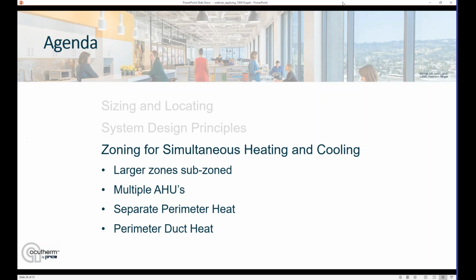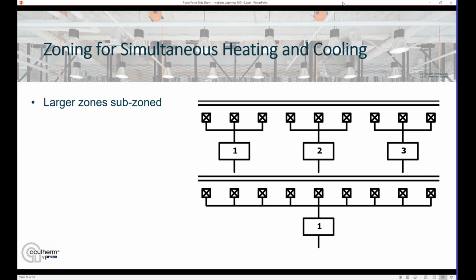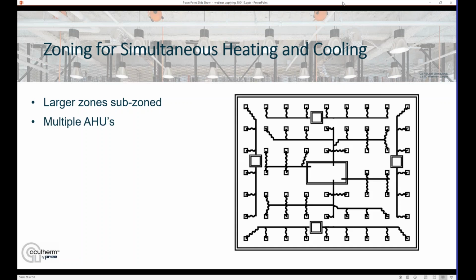Zoning. So you still need to zone the building well. The diffusers themselves can't create hot and cold air, so we need to do good zoning in our space so that we can provide heating when we need to and cooling when we need to. The one thing to keep in mind is with a Therma-Fuser diffuser approach, we are going to create larger zones that are then sub-zoned with the Therma-Fuser diffusers. Each diffuser having the thermostat and VAV damper built in allows us to create these larger zones. And what we want to do is create them by like usage and like exposure so that they're all similar to each other, and we can thus create them as one large zone and allow the Therma-Fuser diffusers to create that individual comfort between the rooms or in the space.